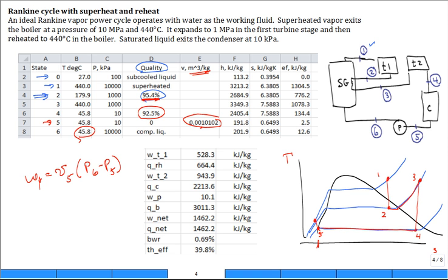Here are the numeric values in kilojoules per kilogram for the work out of the first turbine stage, that reheat, the condenser, the first pass in the boiler or the steam generator, work of the pump, second turbine stage. Q net and W net are both calculated, and they check. And then what we find is that that back work ratio is really small, which is good, 0.7%. And the thermal efficiency is almost 40%, which is good.